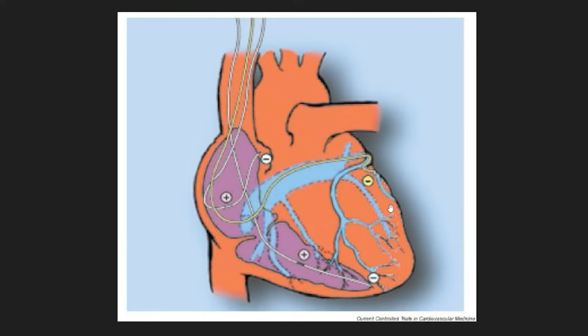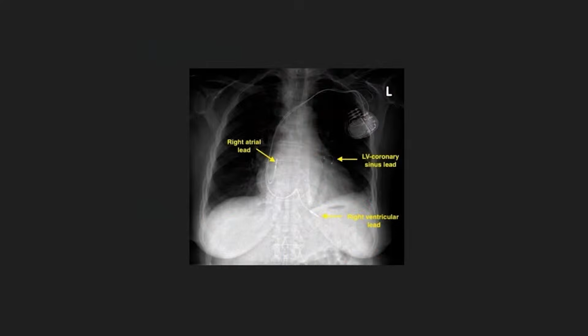And this is the venous blood that's taken from the heart. So remember, the heart sends itself oxygenated blood, and then it takes oxygen away. And then the veins in the heart send the blood back through the coronary sinus and back to the right atrium. So because the coronary sinus opens up into the right atrium, we're able to get to the left side of the heart through this venous system, and we can snake a little lead around. If we're fortunate enough, we can snake it into a certain area where we can then pace the left side of the heart. And so you have a pacemaker lead here on the left side, a pacemaker lead there, and one on the right. So you have communication from the upper chamber and both lower chambers. And the device, the defibrillator, is programmed to time this pacing signal with that pacing signal so they're synchronized. And so when you have that, here's an x-ray.